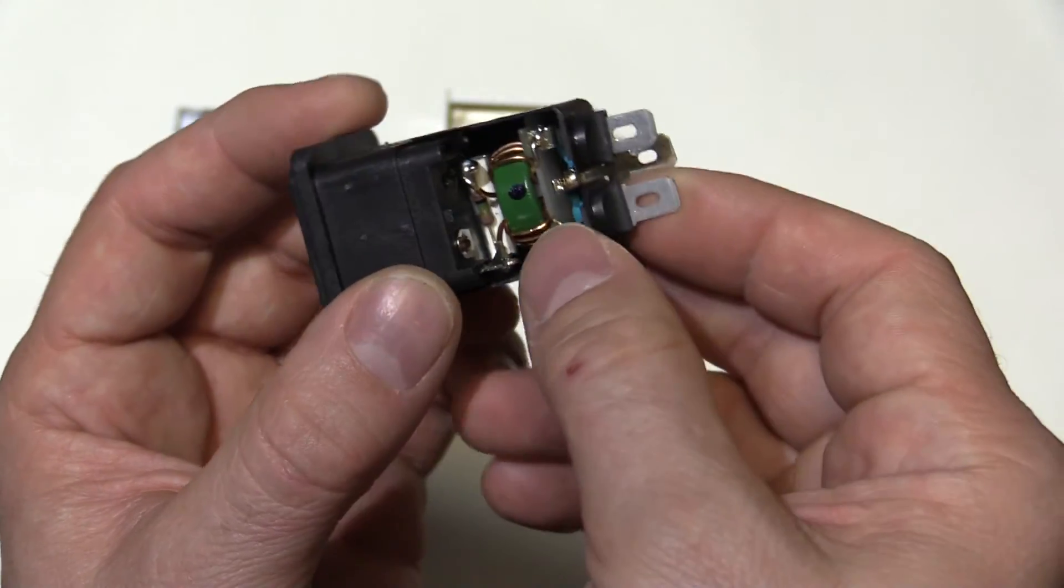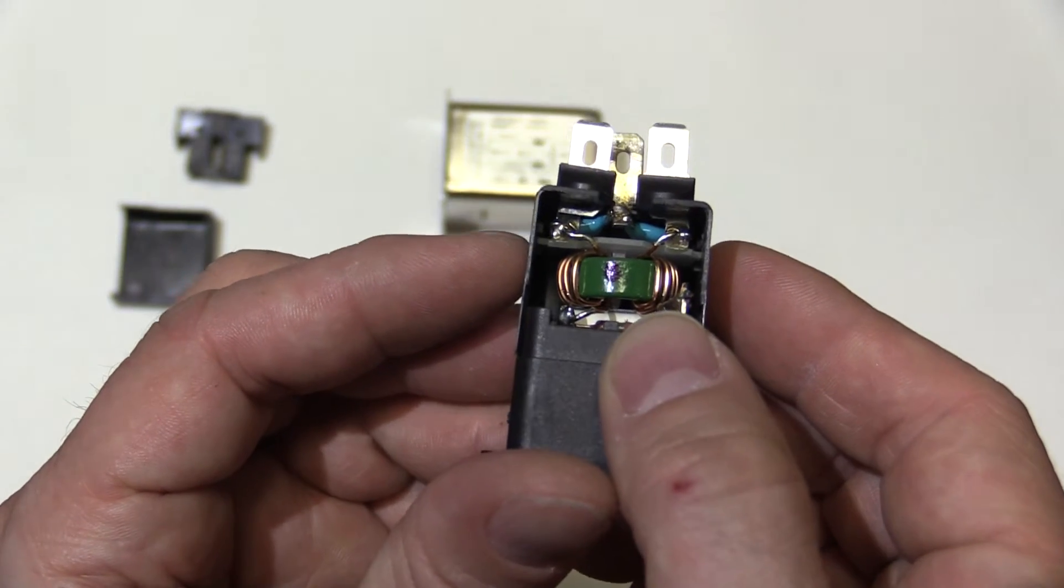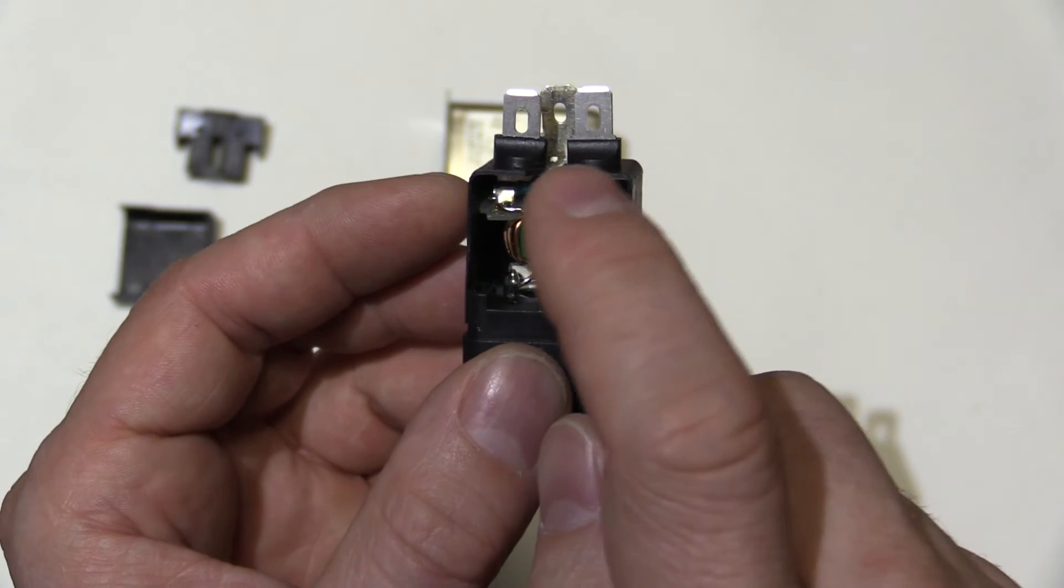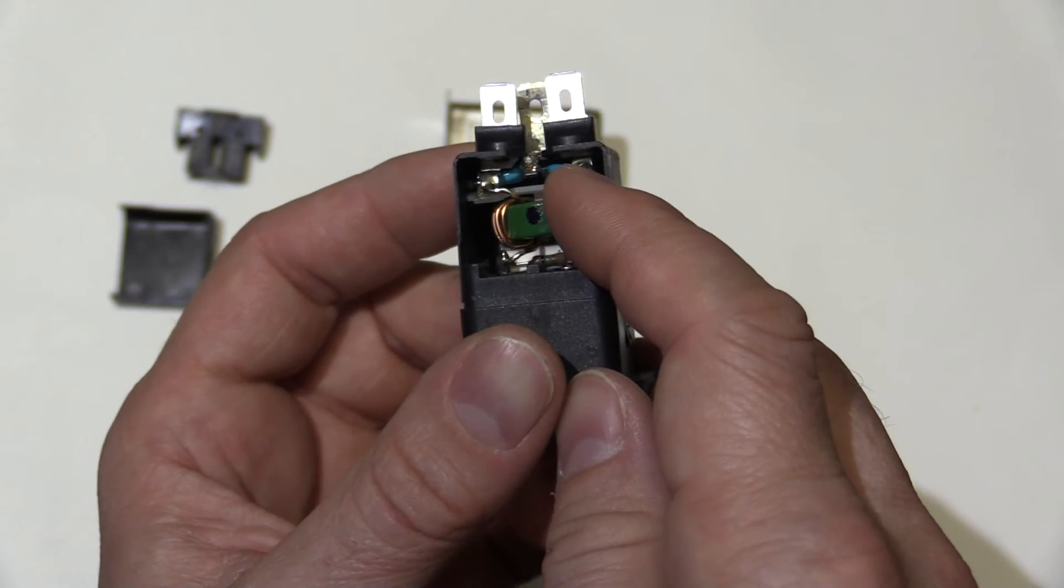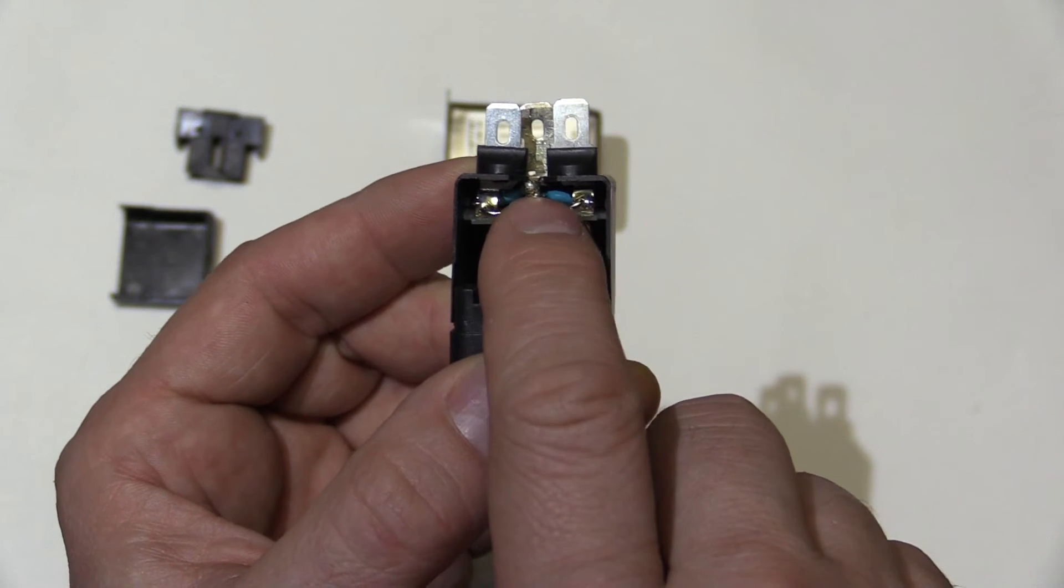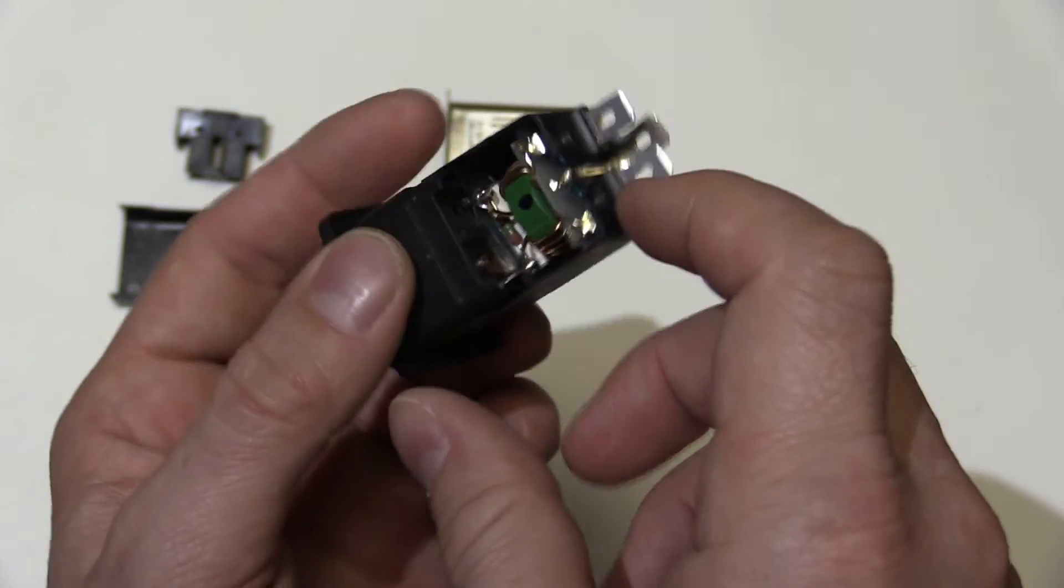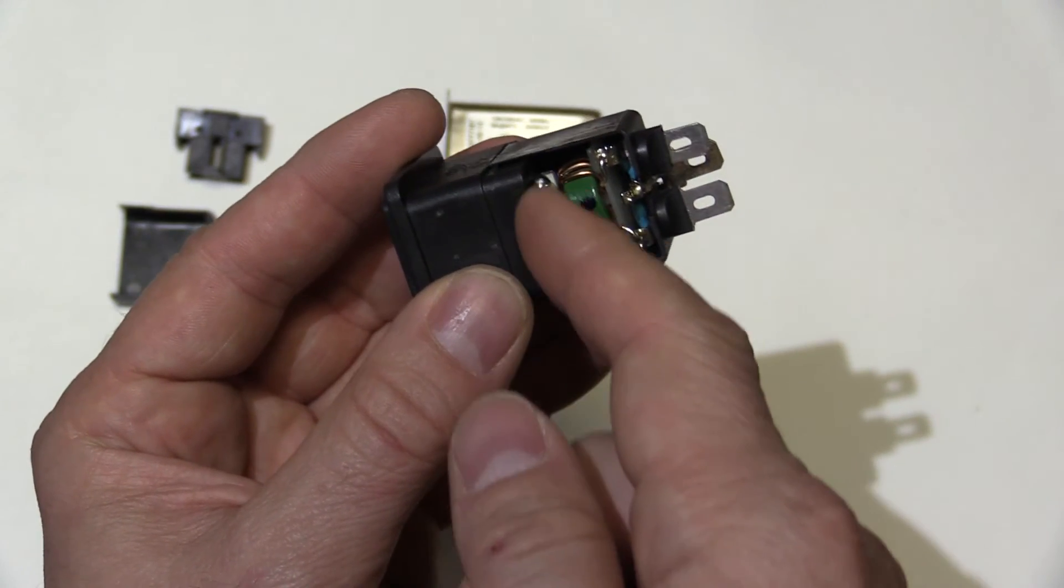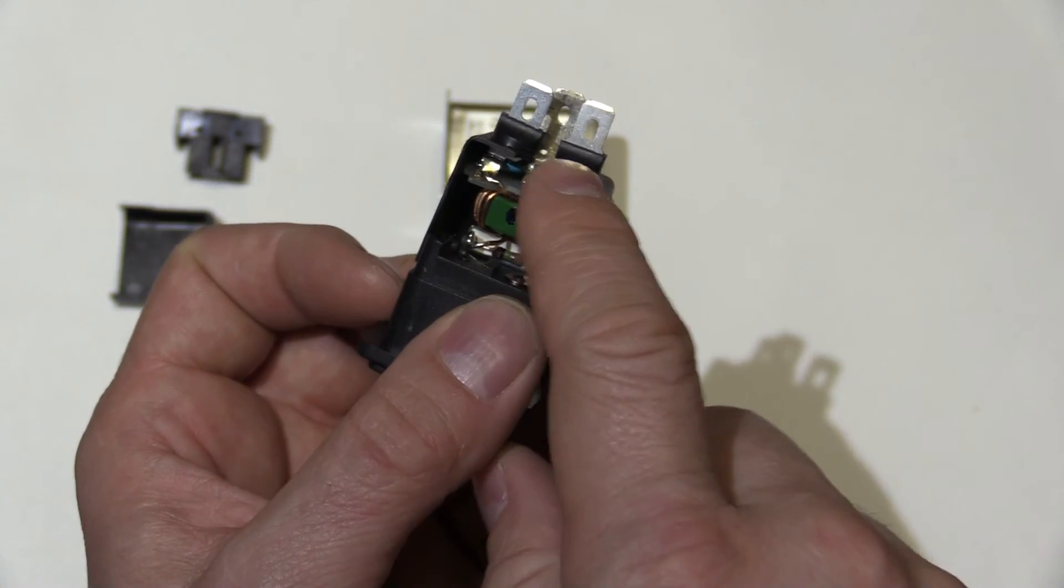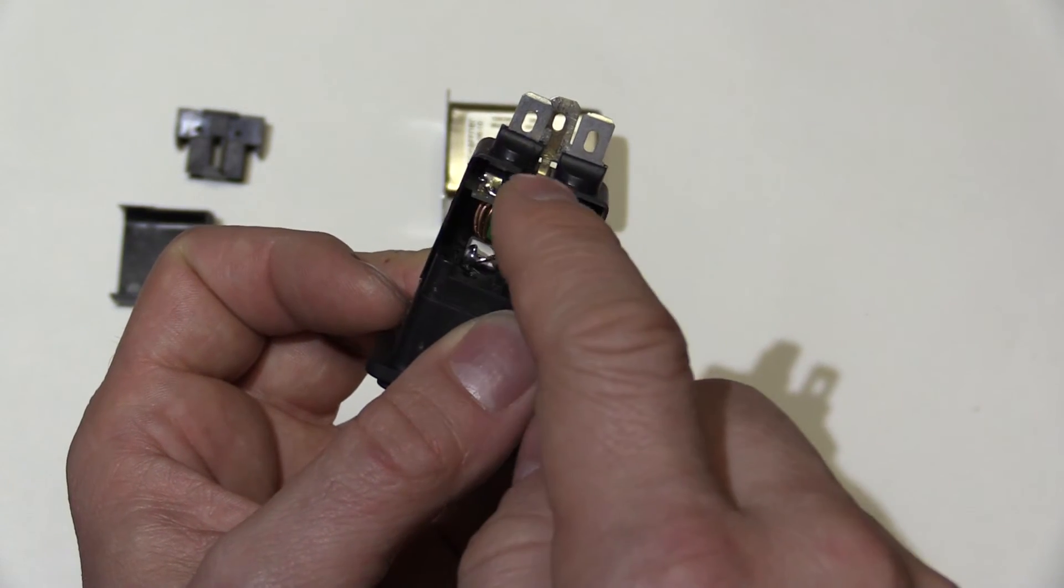Okay, so the next step, you can see the two blue capacitors in there. They're Y class capacitors. They're more like the windshield on your car, you could think. They're designed not to fail, but when they do, they fail safely. The X class capacitor is designed to take a beating across the mains. These ones aren't connected across the mains. They're connected from your active to earth and your neutral to earth.